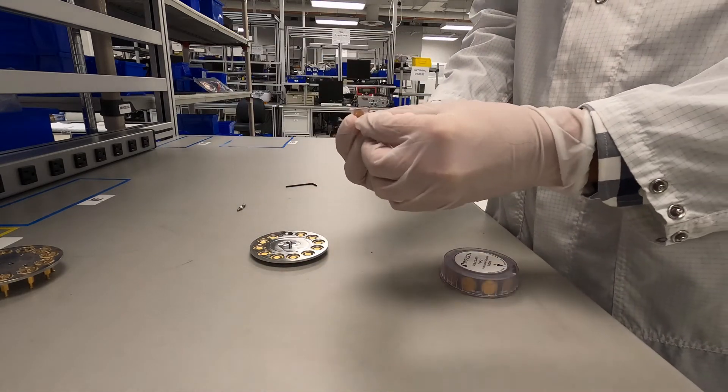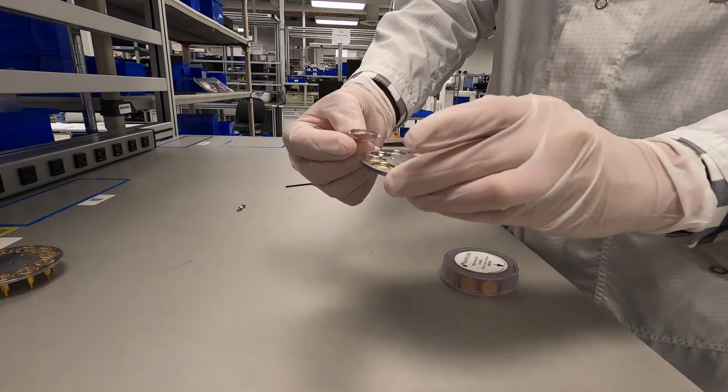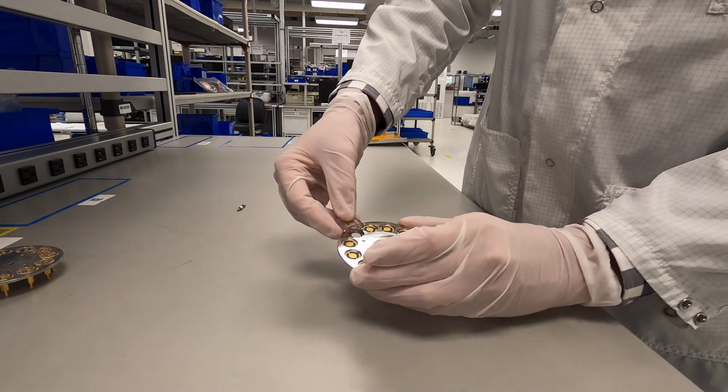Be sure to install the new crystals in the correct orientation such that the full face electrode is facing towards the plate.